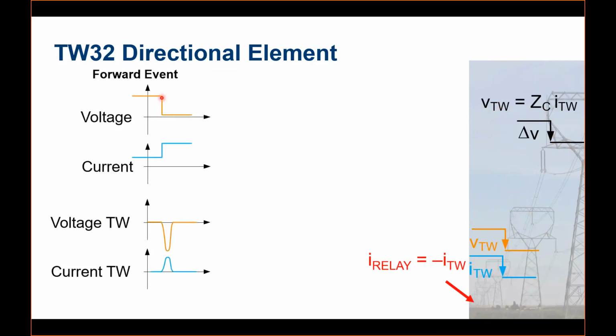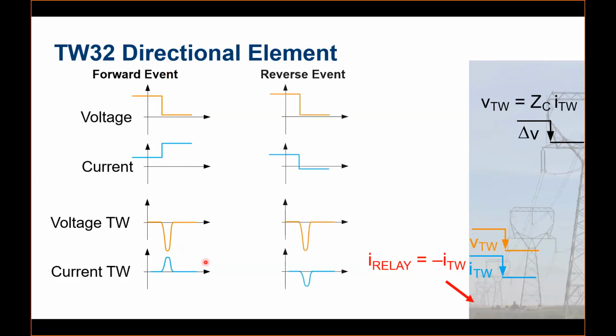So if you get the polarity of the change in the voltage and current in an opposite fashion, similar to our directional concept, it will be decided as a forward fault because the polarities are opposite. And similarly, once you have a reverse fault, you'll get both in the same polarity. So this is just like a polarity comparison, and this is one of the fastest elements available for the directional decision.